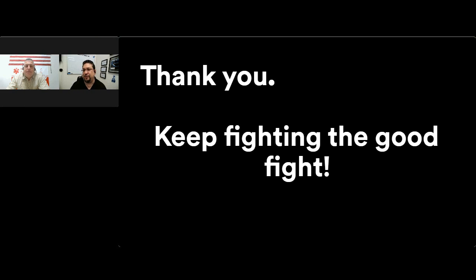First question: what are the most common reasons for sterilization recalls? Is it equipment failure, user error? There's nothing scientifically documented that I'm aware of, but I remember working with folks on the AAMI committees who worked with Getinge, and they used to troubleshoot why equipment failed. A majority of it was pretty much balanced between a failure in the autoclave and human error, which is a large piece of the pie. Under human error, there could be a lot of subsections, but typically it was sterilizer failures.